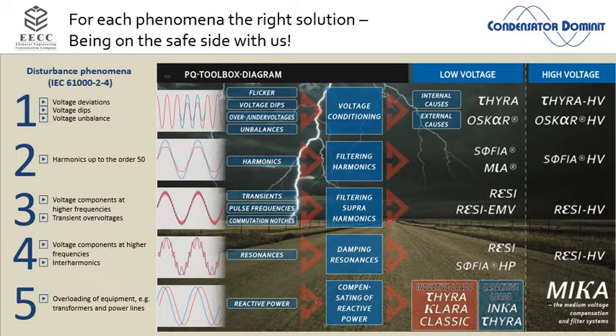Then, number 3 and 4, which is also power quality. It's also described in the norms, but I must admit in the standards, it's a stepchild. When they wrote the standard, they did not really address that issue well enough. We see, and that's just a practical approach, more and more voltage distortions coming from fast switching loads. Nowadays we have megawatt drives with IGBTs at 4 kilohertz. And if you run a megawatt drive on a 4 kilohertz signal, you can see a lot of nonsense in the grid. Solar parks, very problematic.